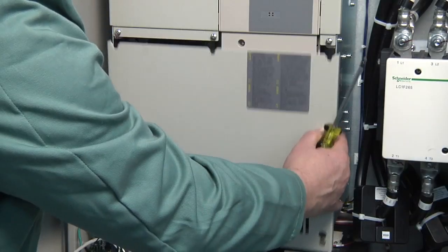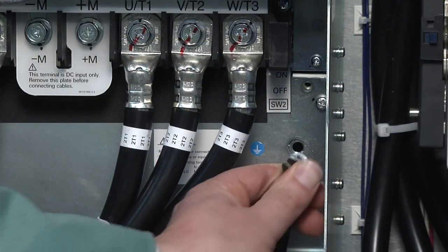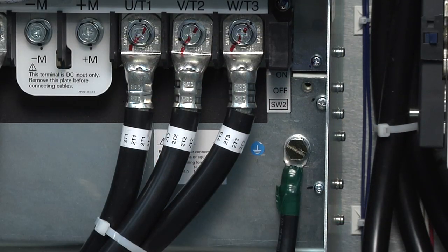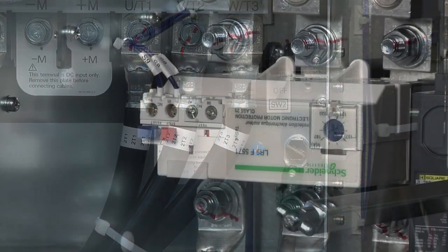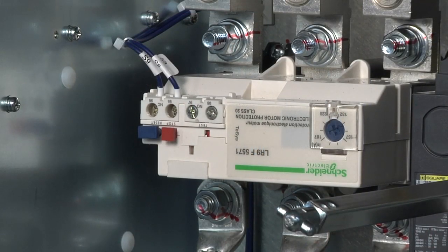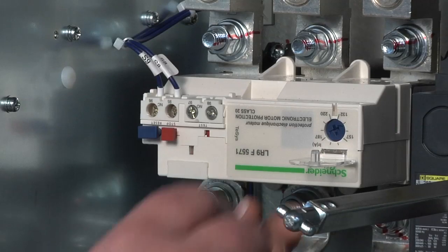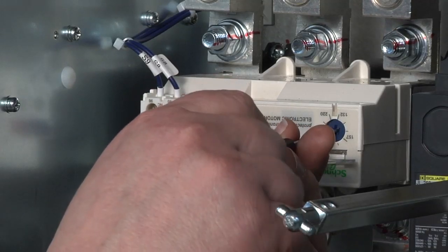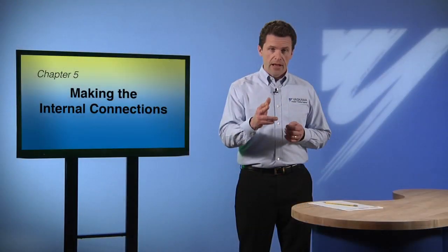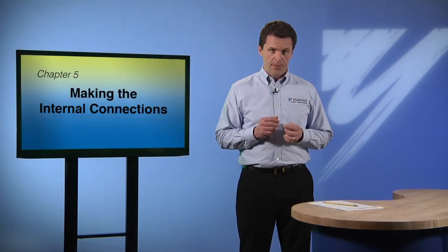Then, connect the motor ground onto the ground lug of the Z1000 drive. After these connections are made, adjust the motor overload to the proper full load amps by turning the dial to the proper value indicated on the motor nameplate. Now you know why we had you write it down.